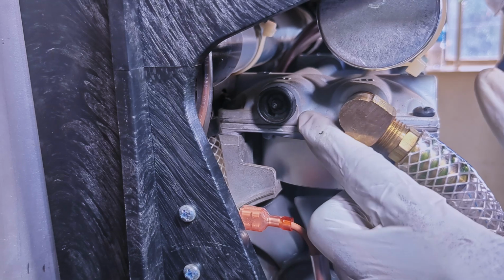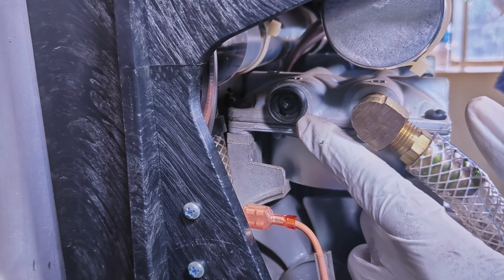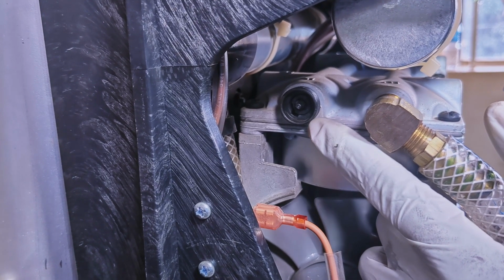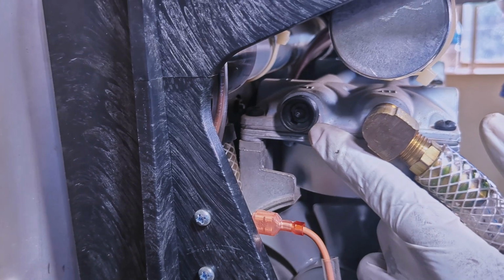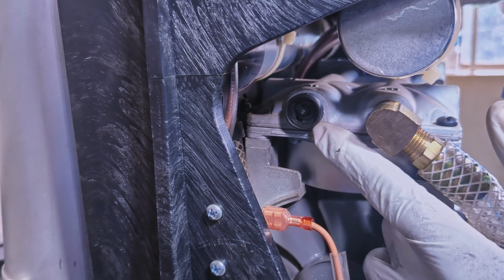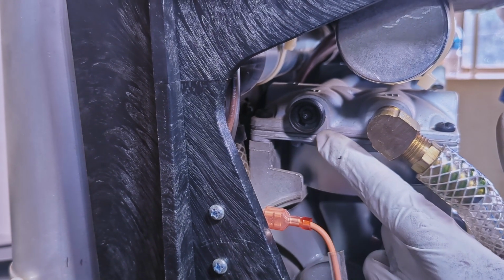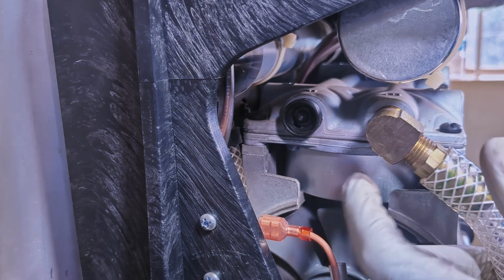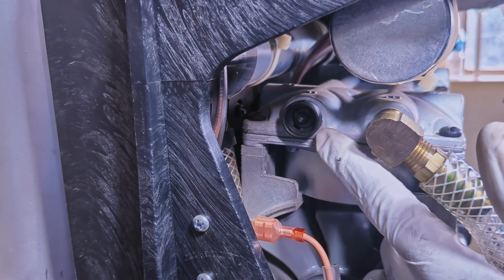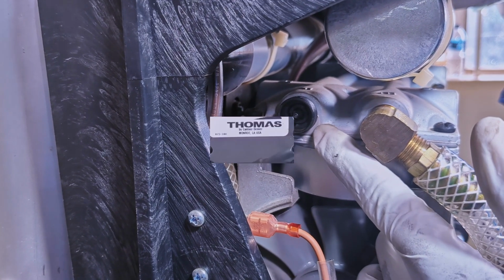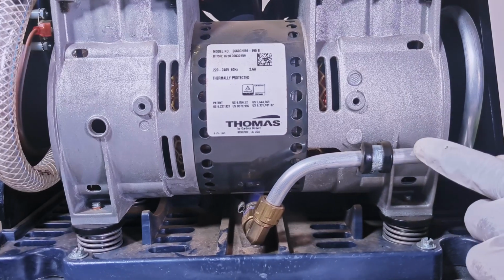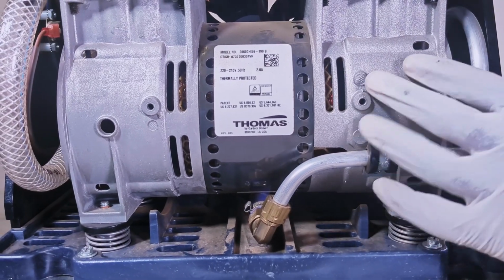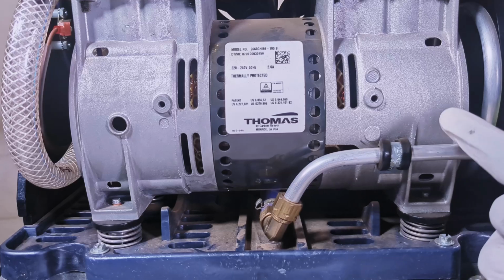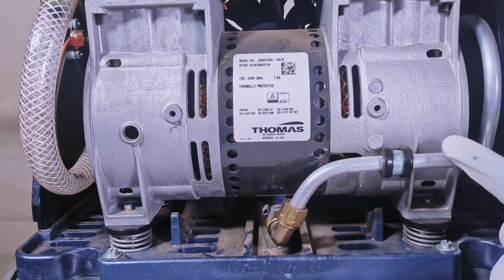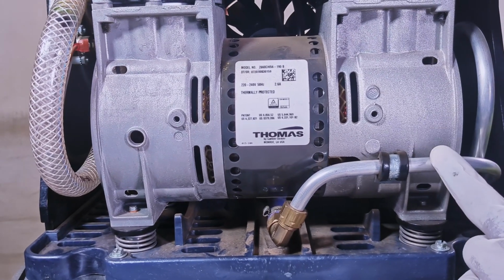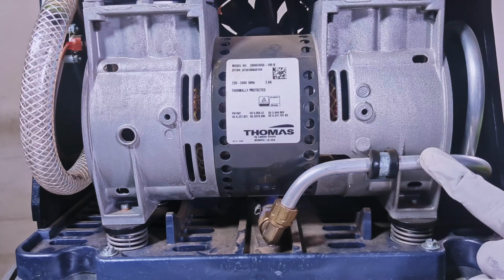The compressor has a pressure relief valve fitted on it. The pressure relief valve is preset at 45 psi. Whenever there is an air pressure of greater than 45 psi in the air compressor, the relief valve will produce a popping sound. There is also a heat exchanger connecting the air compressor and the solenoid valve. This heat exchanger is used to reduce the temperature of the compressed air by dissipating heat.